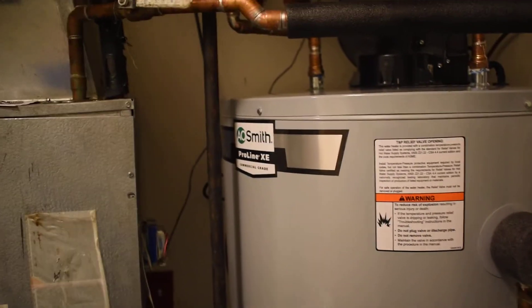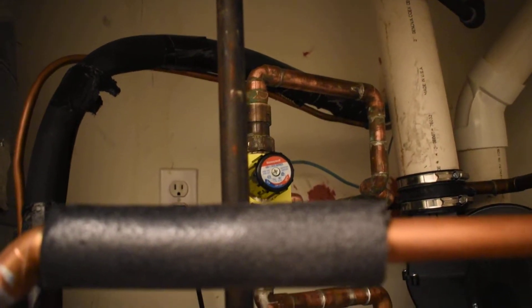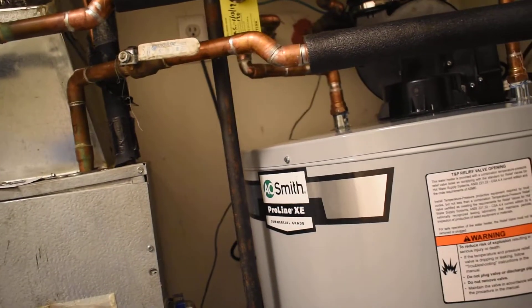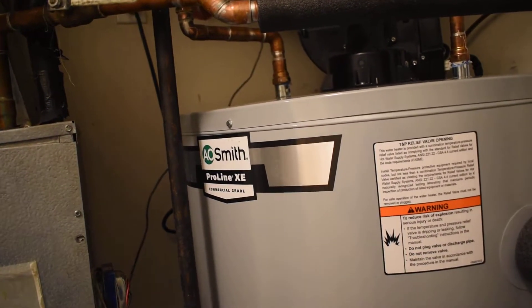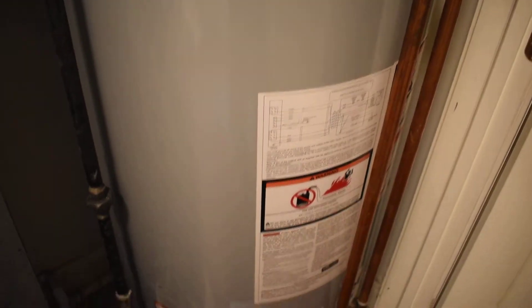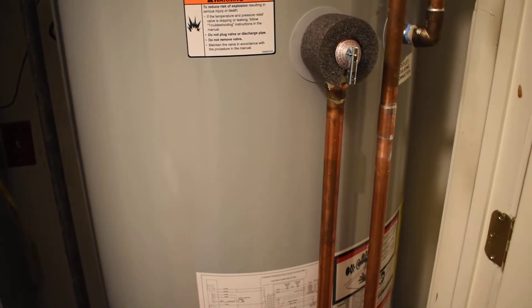It also turns out that the water going to the house was too hot, so they had to install a new mixing valve. And when they took the old one out, it turns out it was clogged as hell — so that wasn't good. But when they came, they installed that new fitting and gave the boiler a couple tests and everything works good.